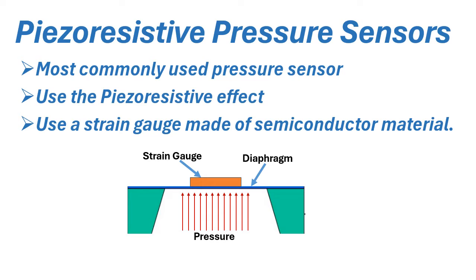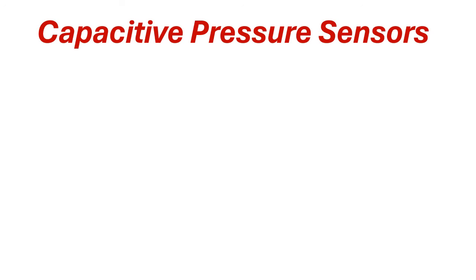When pressure is applied to the diaphragm, the strain gauge is stressed along with the diaphragm. When the strain gauge is stressed, its electrical resistance changes. This change in resistance corresponds to the applied pressure. This is the basic working principle of the piezo resistive pressure sensor.